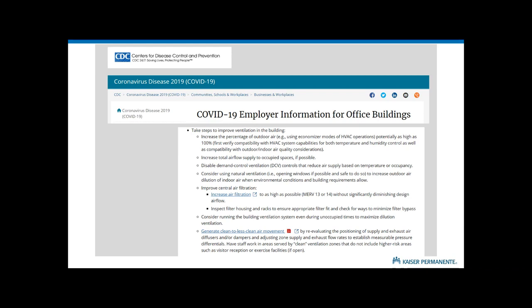Number 1, increased percentage of outside air. Number 2, increased total airflow. Number 3, disable your demand control ventilation systems. Number 4, use natural ventilation. Number 5, increase your filter efficiencies. Number 6, inspect filters for bypass - that's always a good idea, by the way. Number 7, consider running your ventilation systems all night, 24/7, and of course you go, oh my God, there goes your energy. And then the last one, create negative pressure zones, right?